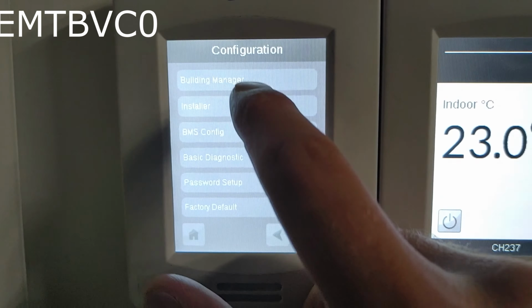If you watched the video up to this moment, let me show you another way how to find out ESP setting value. This is the LATS program. This is a free software for LG multi-V systems design. Let's go. Same conditions. 6-ton high static ducted type indoor unit, and we need to set up 0.7 inch of water gauge static pressure and 2000 CFM airflow.